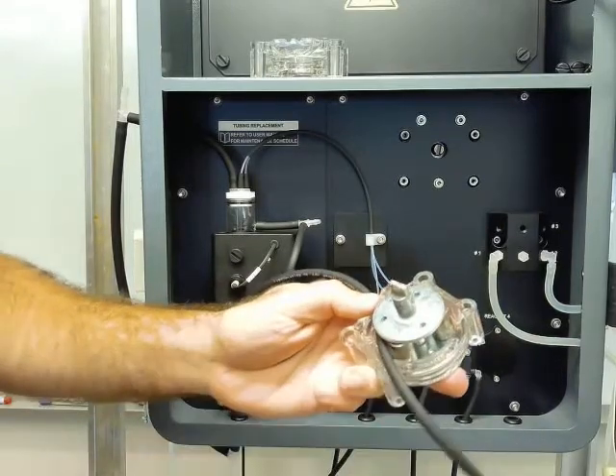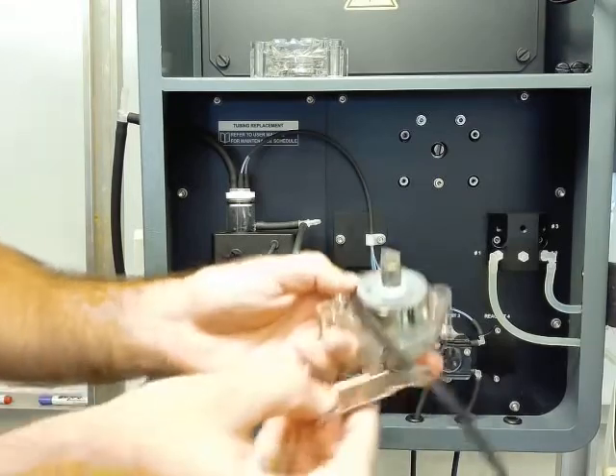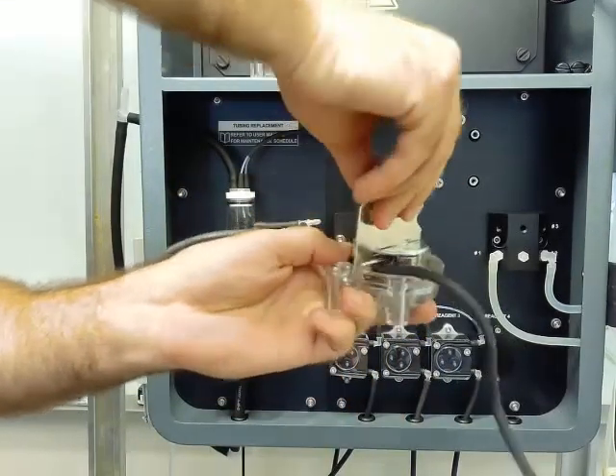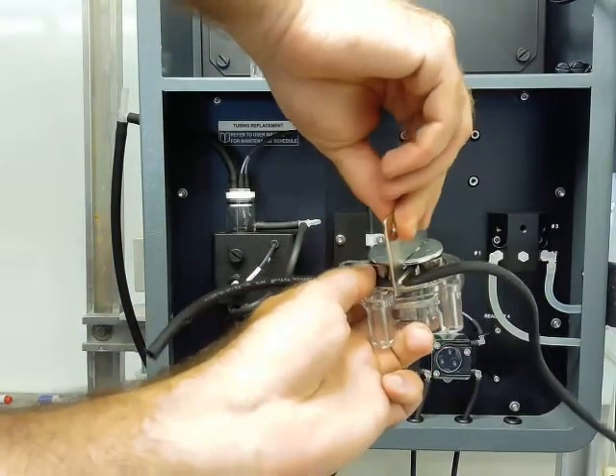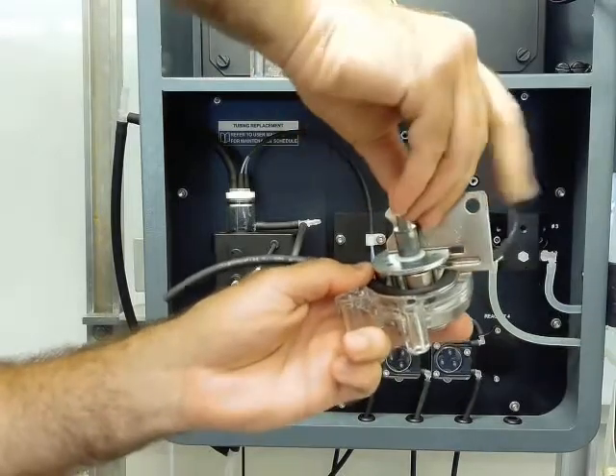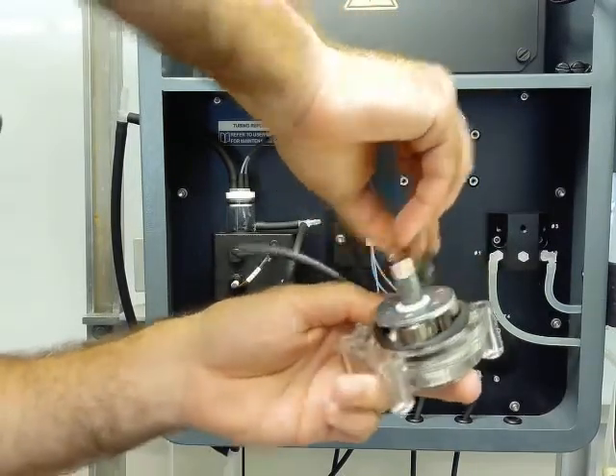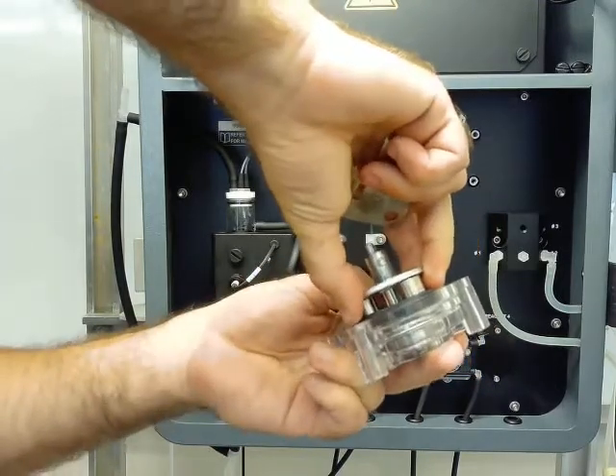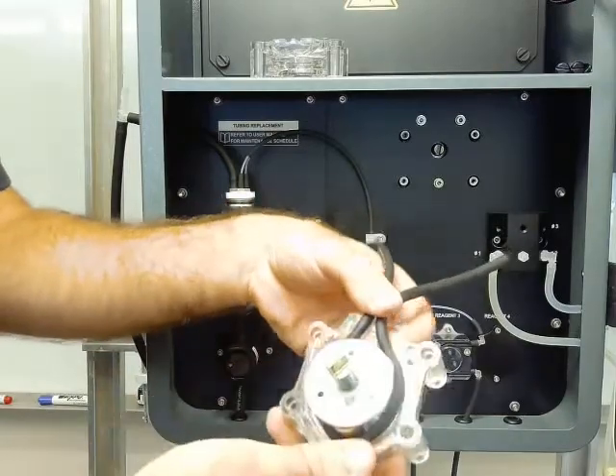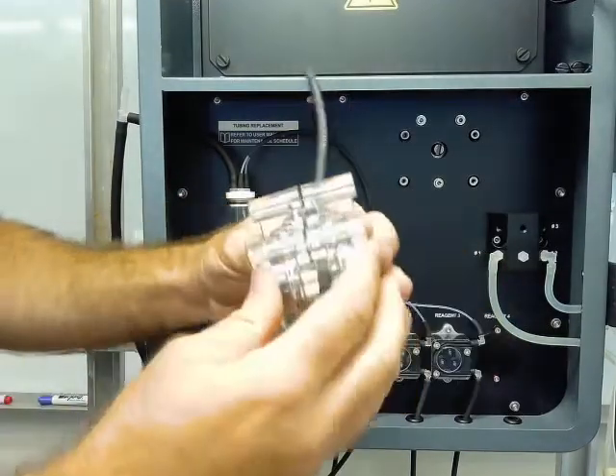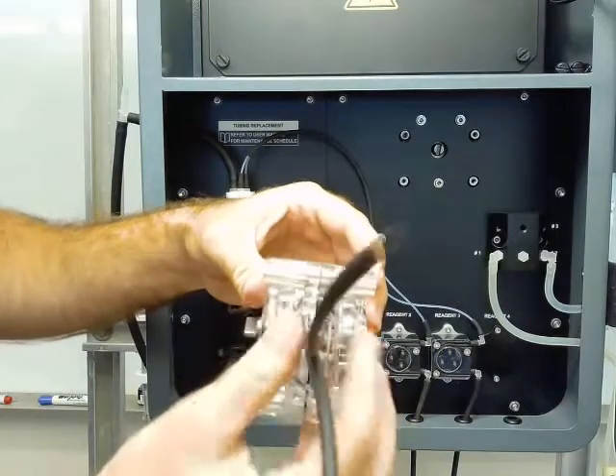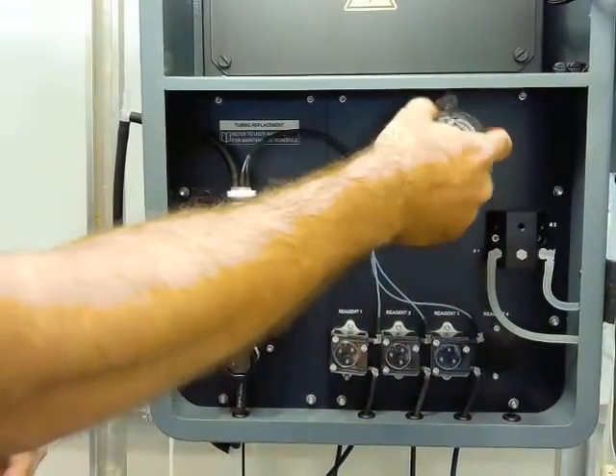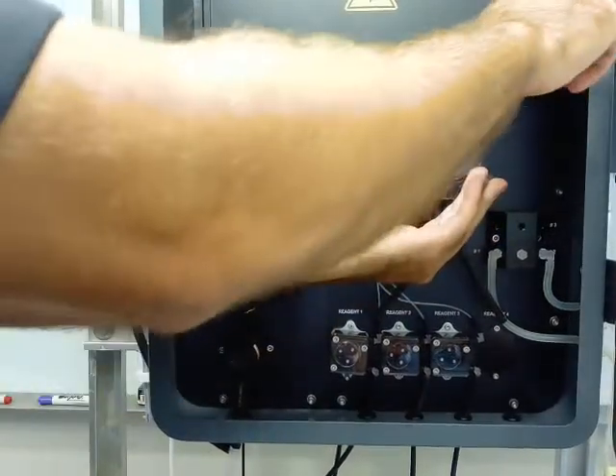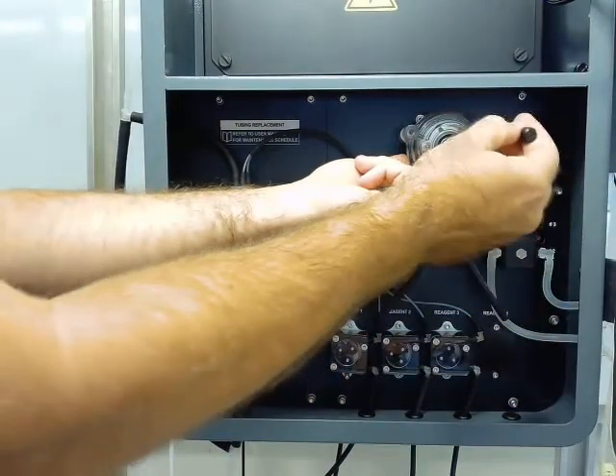Once we get one end, we hold one end of the tubing in place at the inlet, and then this tool slides into place between the rollers and then against the pump head. Then as we rotate, it forces the tubing against the rollers and then into the pump head body. Once we get that, we can line up our inlet and our outlet again. And then once we add our other half of the pump head, just press it together again. Just make sure we don't pinch the tubing, inlet, or outlet. And once we've got that together, line up our groove for our motor back in place. Make sure we've got the right amount of tubing on both sides, and then put our screws back in place.